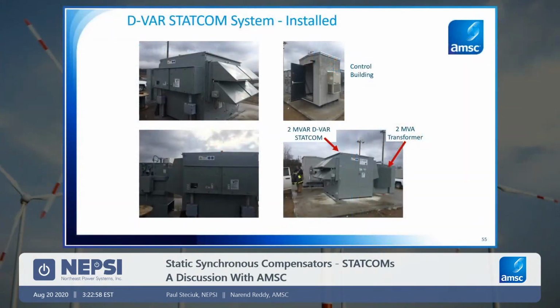Okay, so this is a slide just showing some pictures of the installation. As I mentioned, this is a 2 MVAR DVAR unit, but as you can see, the size of the STATCOM is really the same box as for the 4 MVAR. Half of the box is inverters, just sized for the application. But the transformer that we selected for that is a 2 MVA, as you can see in the bottom right picture. So this gives a couple of different angles in terms of the installation requirement.